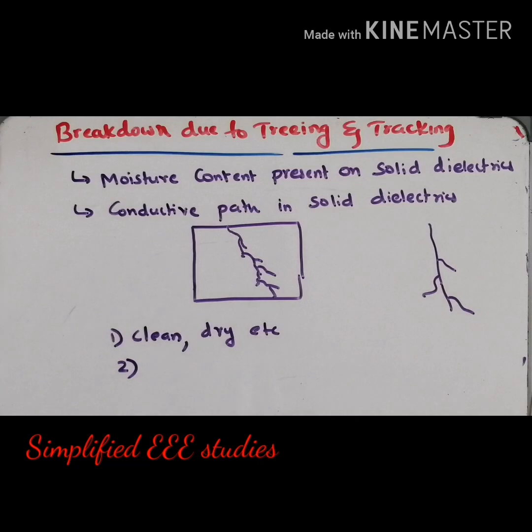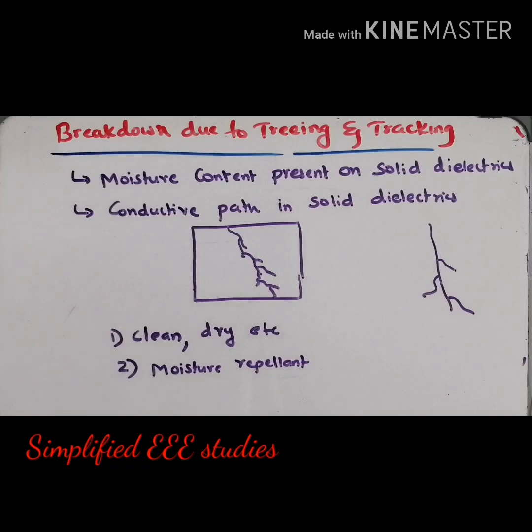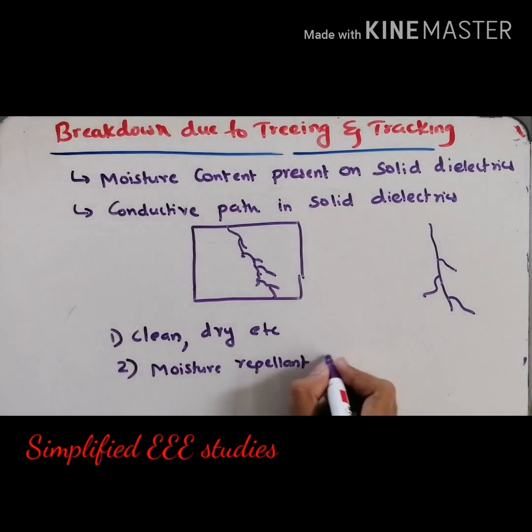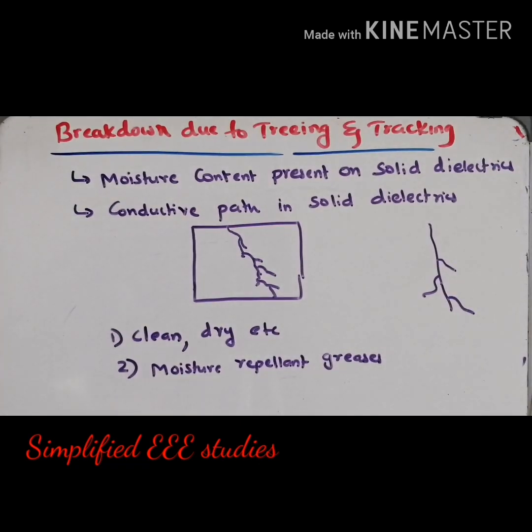It is also advisable to use moisture repellent greases, such that you can protect the solid dielectric material against moisture content. If you avoid moisture content, obviously you can get rid of the treeing and tracking phenomenon. This type of breakdown is generally known as treeing and tracking.